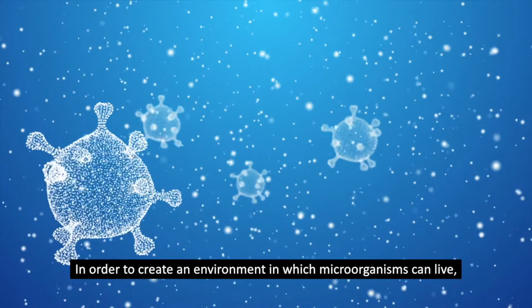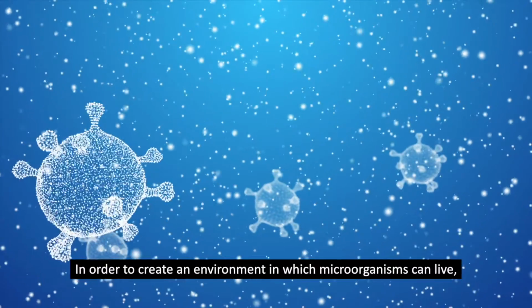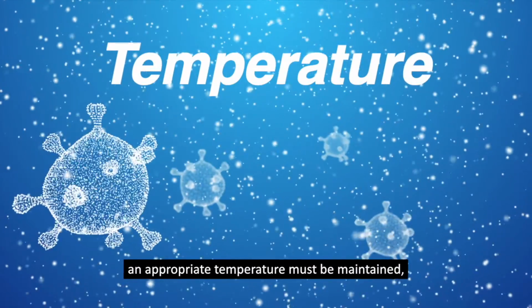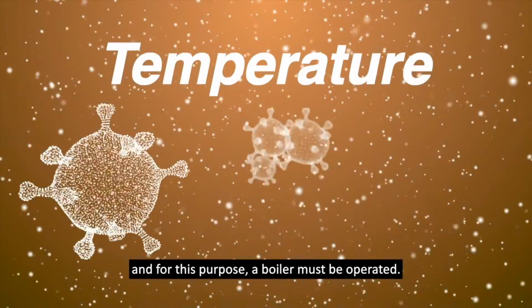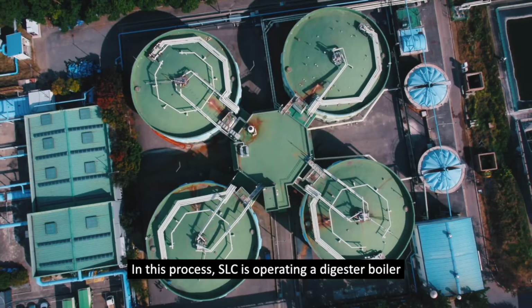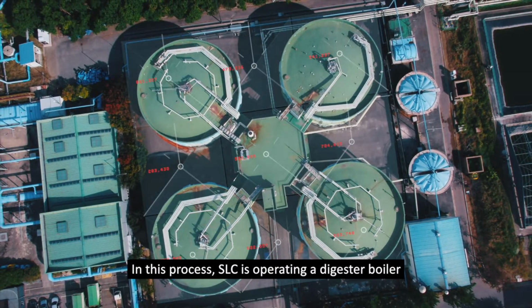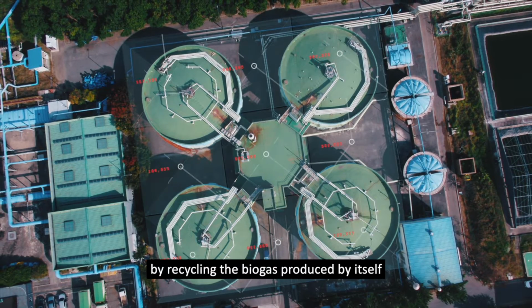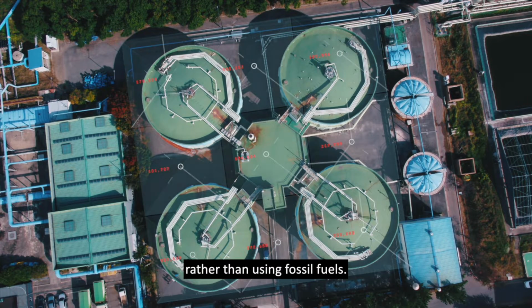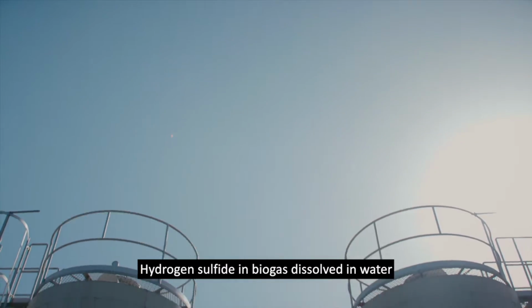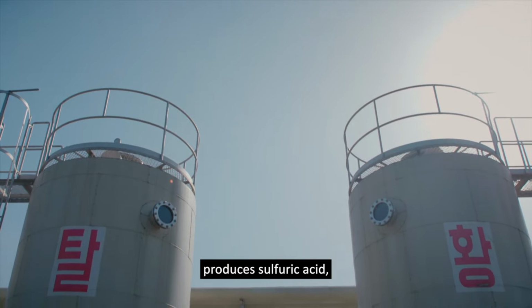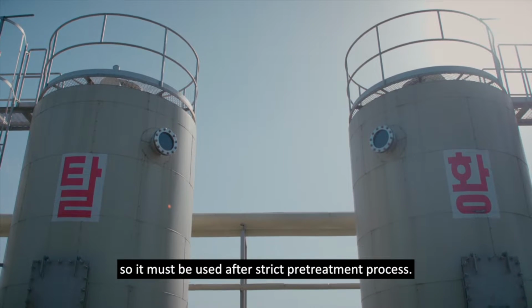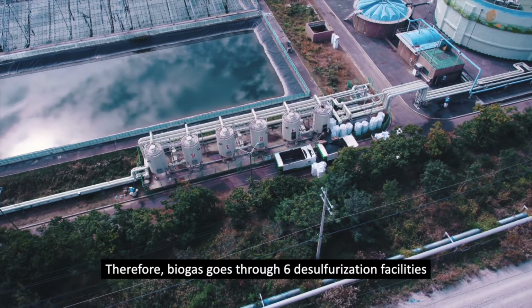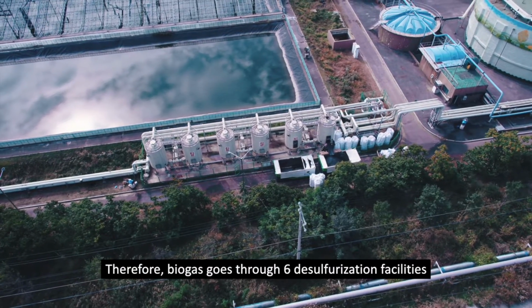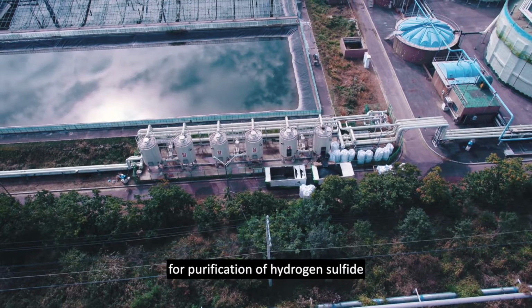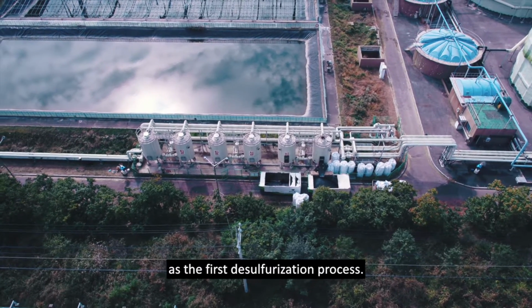In order to create an environment in which microorganisms can live, an appropriate temperature must be maintained, and for this purpose, a boiler must be operated. In this process, SLC is operating a digester boiler by recycling the biogas produced by itself, rather than using fossil fuels. Hydrogen sulfide in biogas dissolved in water produces sulfuric acid, so it must be used after a strict pretreatment process. Therefore, biogas goes through 6 desulfurization facilities for purification of hydrogen sulfide as the first desulfurization process.